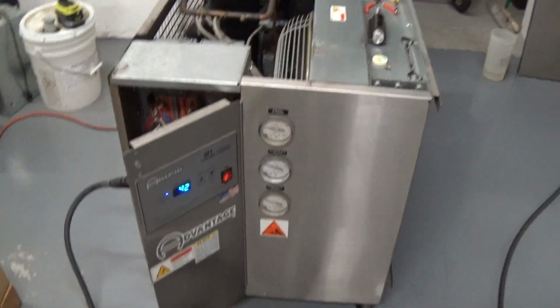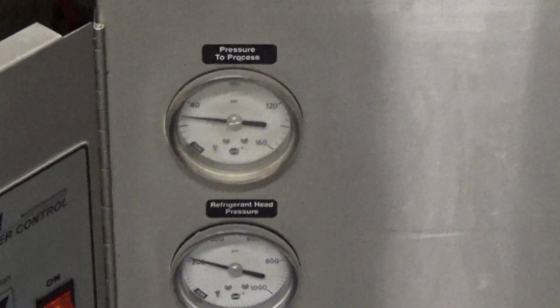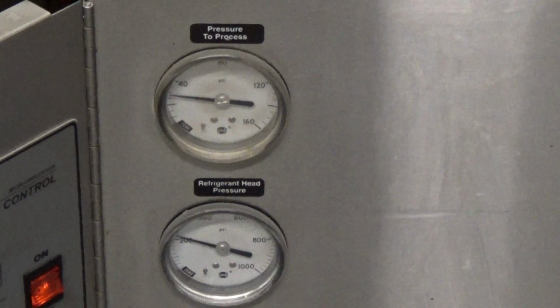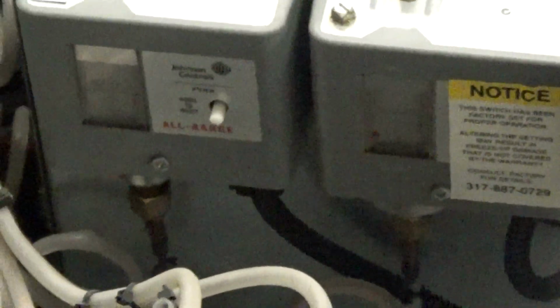This unit, like I said, we've tested before, but I just want to double check it goes down to that lower temperature. My technician Dana adjusted the pressure switches. On the left there, that's the low. On the right, that's the high. That's a reset switch there. We do have the top cover, of course, just set off over to the side there.